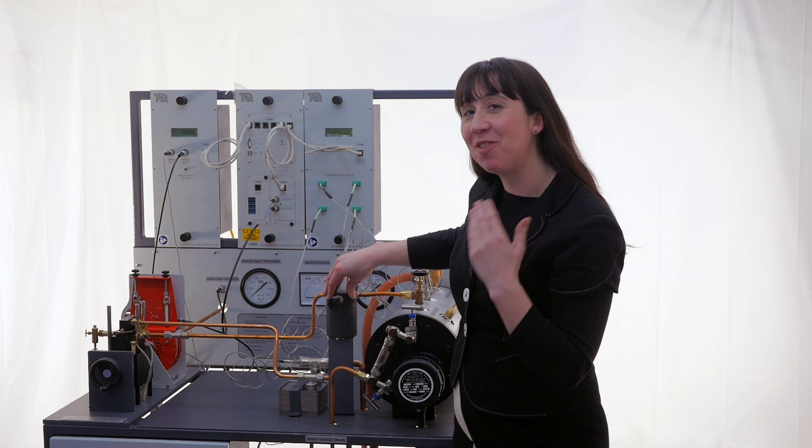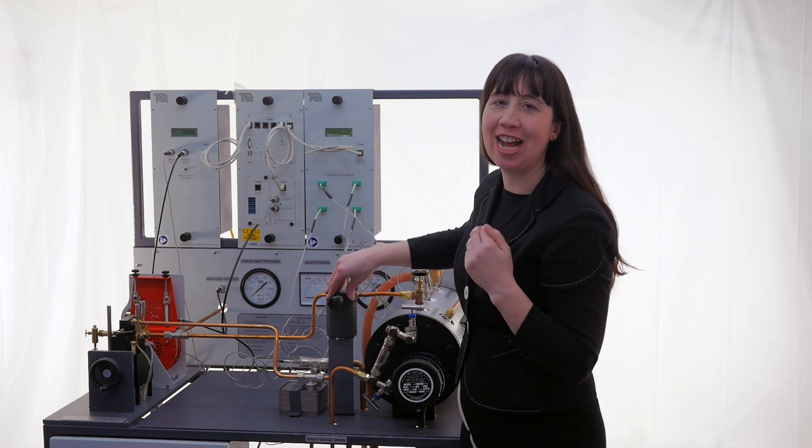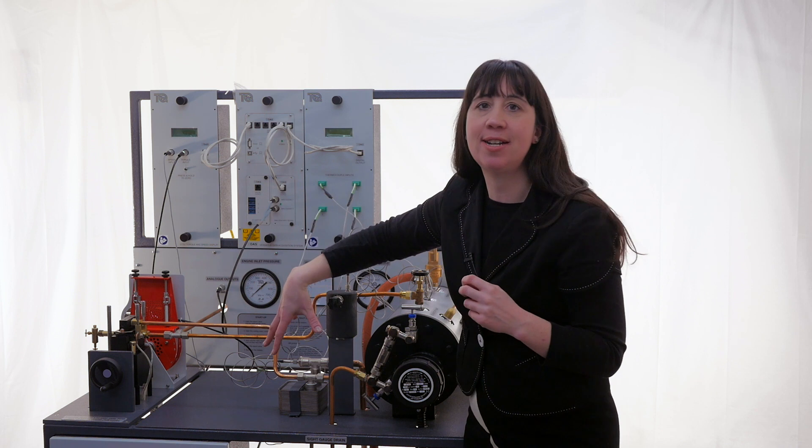When using the calorimeter here for dryness fraction testing, the outlet steam passes through the condenser. The condenser cools this steam so only water passes down to the waste tank.